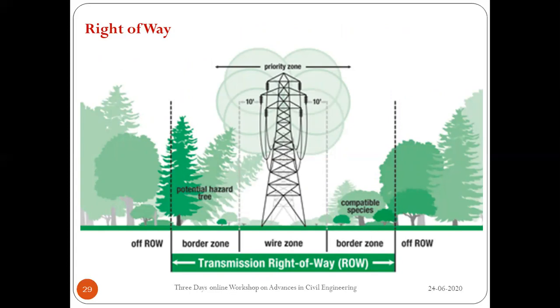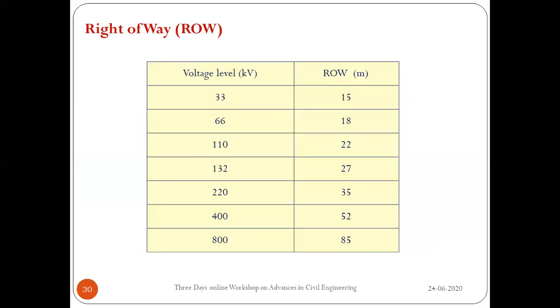Broken wire condition is when one or more wires are cut off — towers must be designed for both normal and broken wire conditions. The right of way image shows the wire zone between cross arm ends, with border zones on either side; together they form the transmission corridor. In India, for a 400 kV line, the total right of way is 52 meters — 26 meters on either side from the tower center.